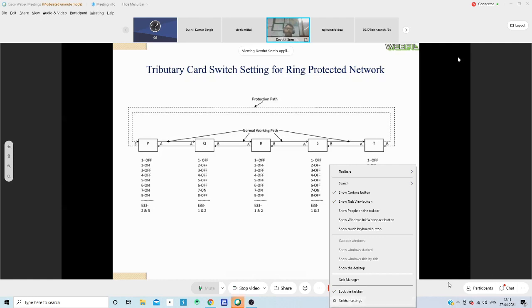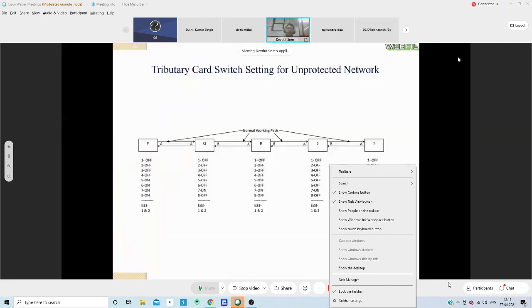So there is no change in any of the intermediate stations. The only change has to be done in the 2 end stations. Only 2 changes need to be done. That is, dip switch number 2 has to be switched on in both ends, and the E33 jumper has to be set in pin number 2 and 3. To implement the ring protection, only the 2 terminal stations' configuration has to be changed. All other stations, no need to change anything. Okay. So up to this, are there any clarifications or questions?